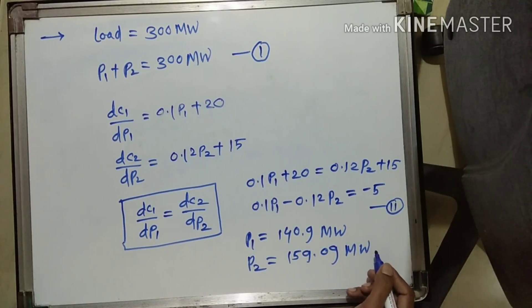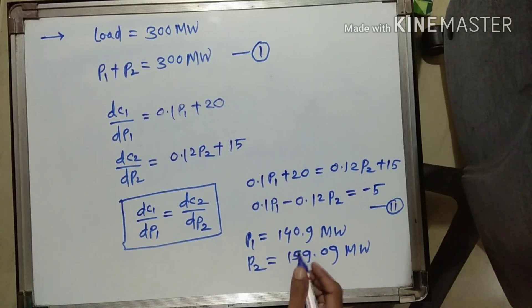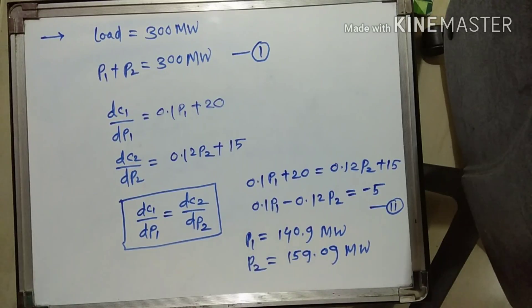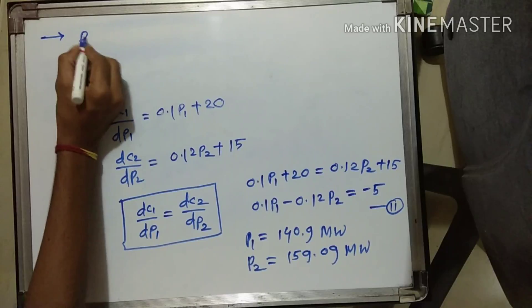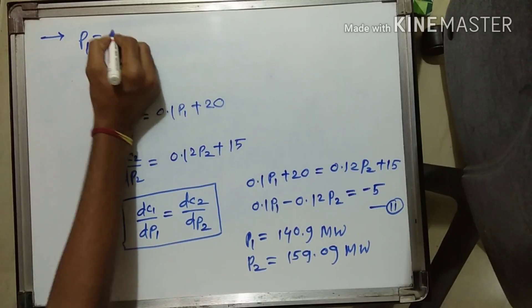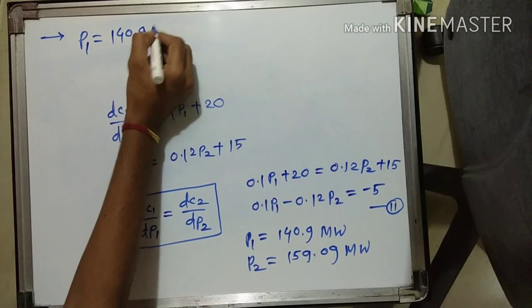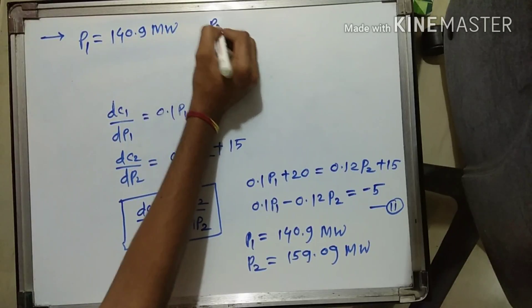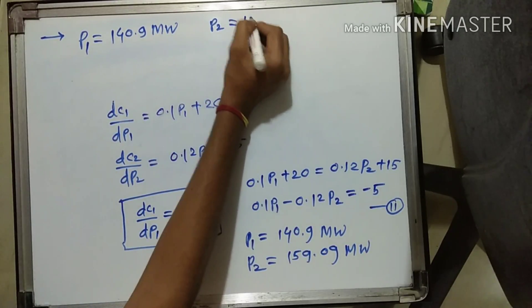Hence, we have solved the first part of the question. This is the most economical load division between generator 1 and generator 2: P1 = 140.9 megawatt and P2 = 159.09 megawatt.